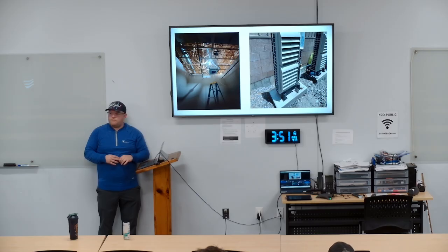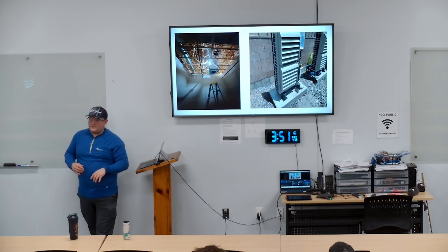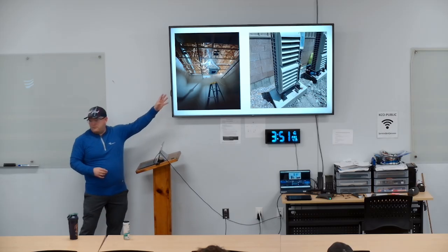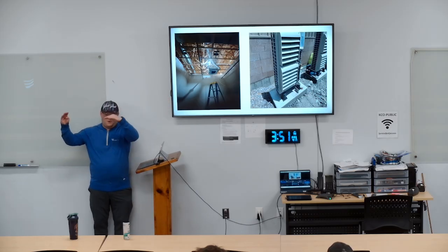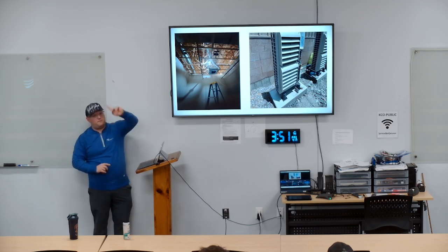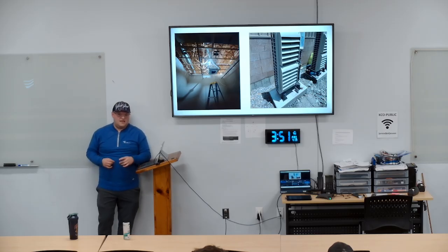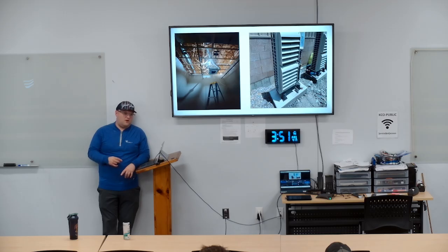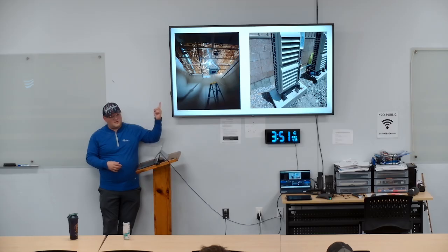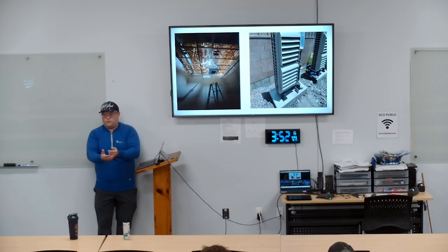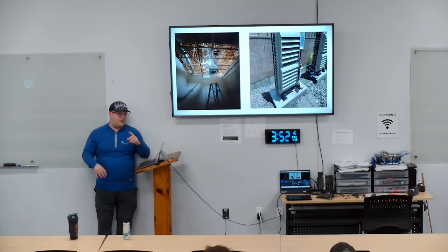So is that, to add a pump on something like that? Sometimes we did. They've got a pump built in. We pumped it up, and we put another pump on top to pump it in. The negative with that is, anytime you have 2 pumps installed in one system, have fun with that alarm. That alarm wire that goes off when it says, hey, this pump's bad, is hard to tie. Their pump's internal, and they have it tied into their control board. We have an external pump that now we've got to tell the other pump to turn off when this one goes bad, and it turns into a nightmare.